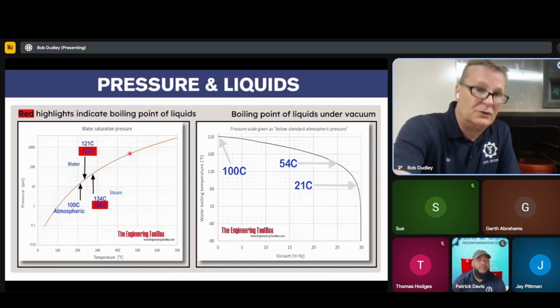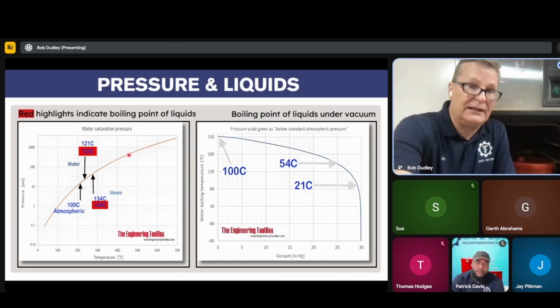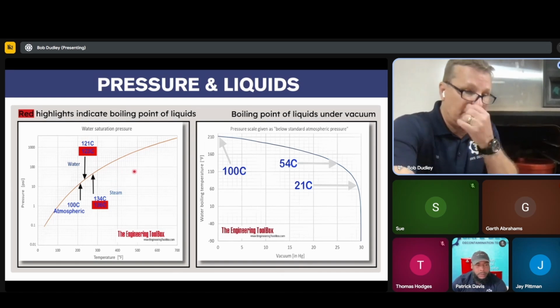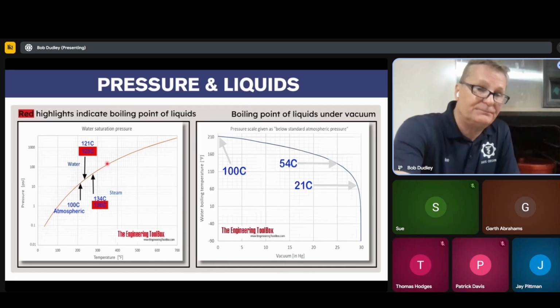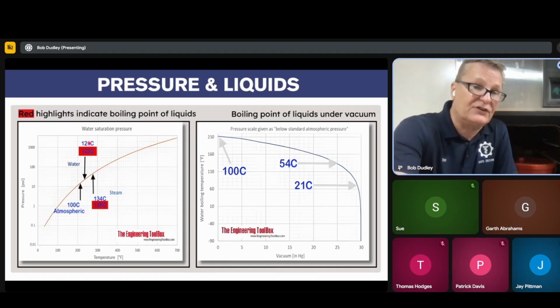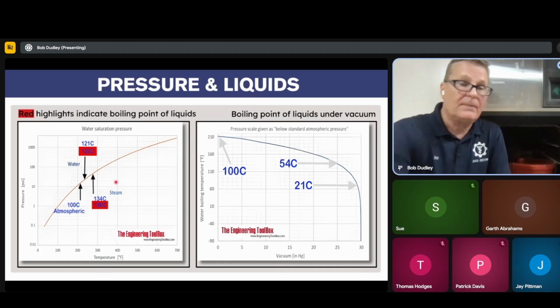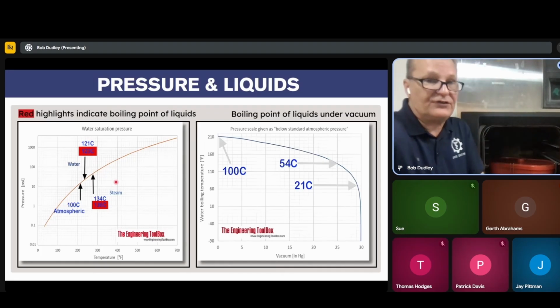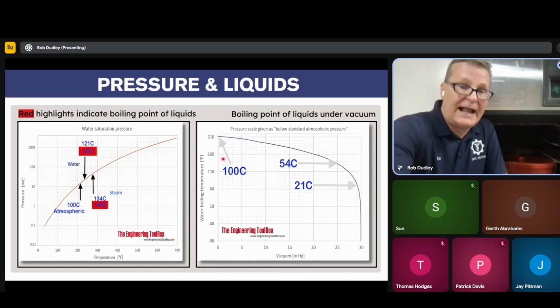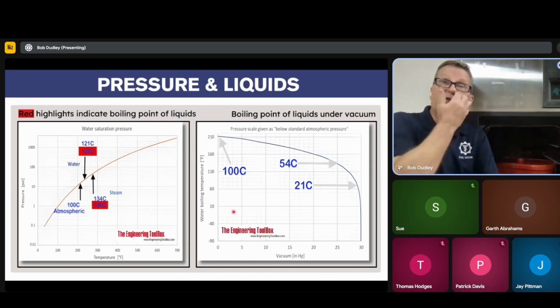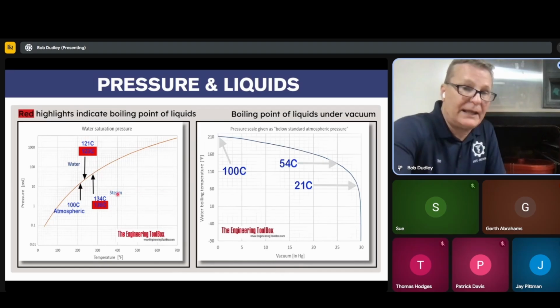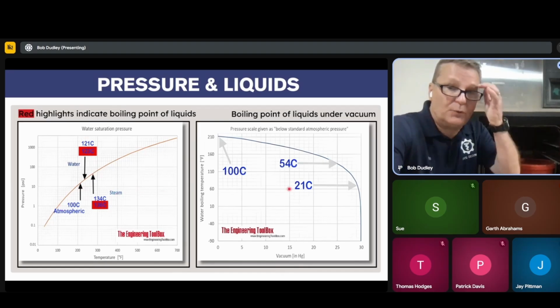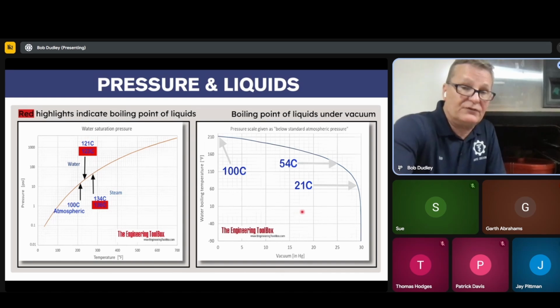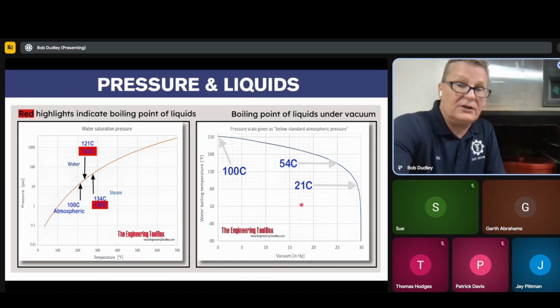And this is critical, especially since some people add liquids to their waste in hopes of producing steam to get it to sterilize. Now, if you do get the steam, this is the temperature of your steam, and this is the temperature of your water. So let's look at the reverse of this. When you start pulling a vacuum on the other side, this is where the drastic change takes place. I really want you to pay attention to these two charts more than anything, because this is very, very critical when understanding your cycles.